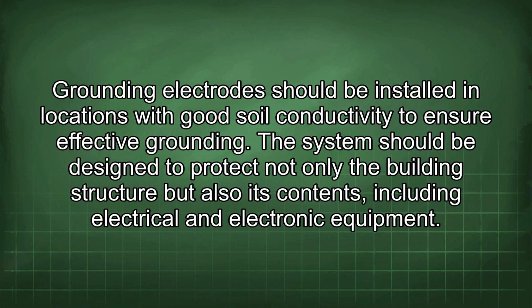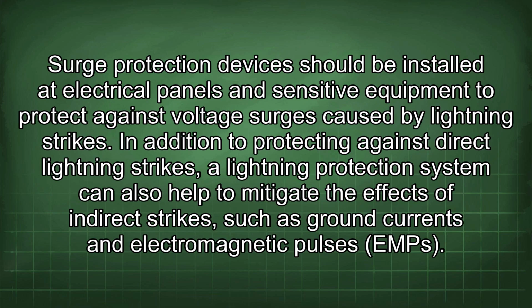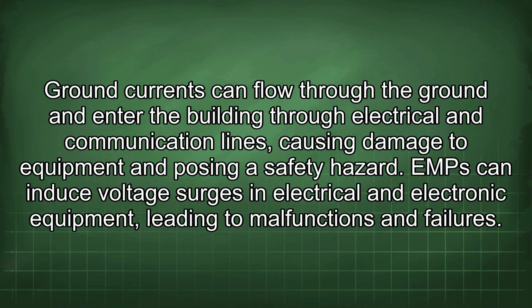The system should be designed to protect not only the building structure but also its contents, including electrical and electronic equipment. Surge protection devices should be installed at electrical panels and sensitive equipment to protect against voltage surges caused by lightning strikes. In addition to protecting against direct lightning strikes, a lightning protection system can also help to mitigate the effects of indirect strikes such as ground currents and electromagnetic pulses (EMP). Ground currents can flow through the ground and enter the building through electrical and communication lines, causing damage to equipment and posing a safety hazard.